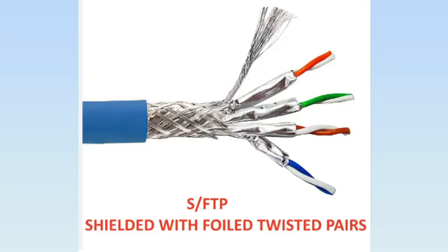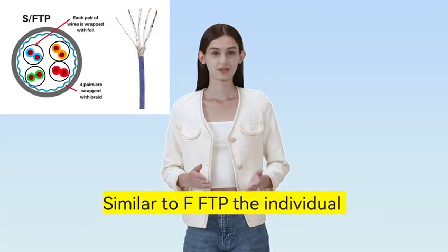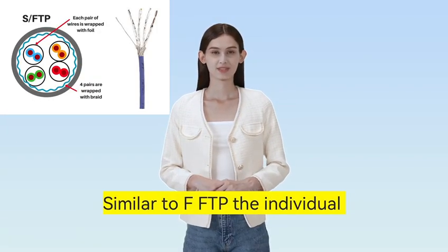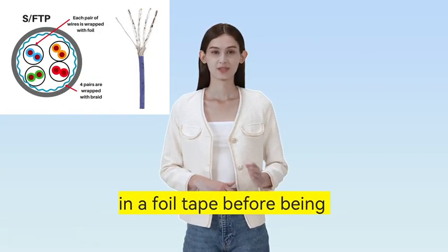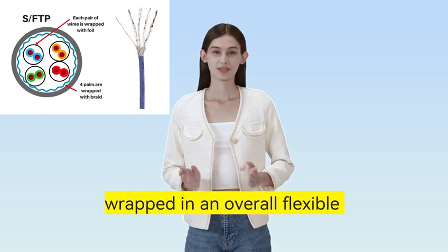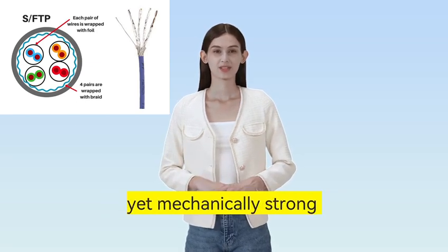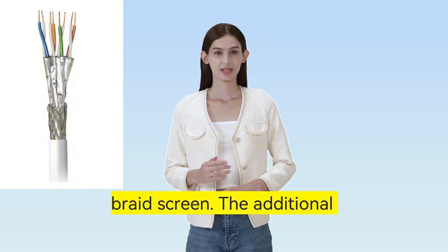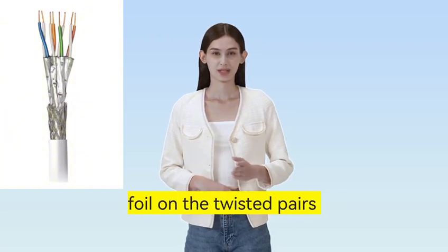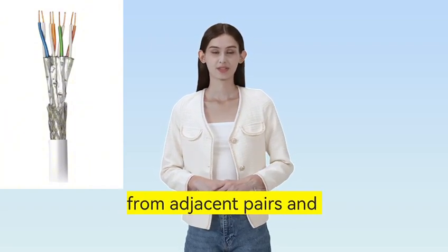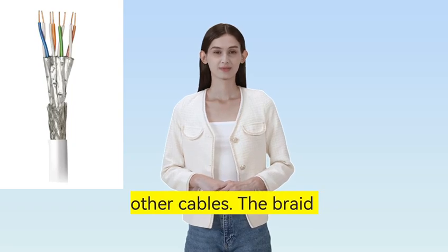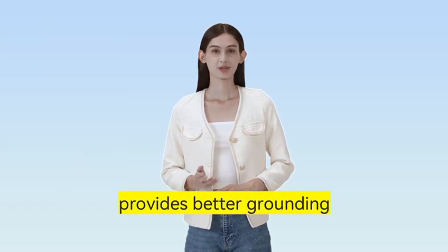S/FTP, shielded with foiled twisted pairs. Similar to F/FTP, the individual twisted pairs are wrapped in a foil tape before being wrapped in an overall flexible yet mechanically strong braid screen. The additional foil on the twisted pairs helps to reduce crosstalk from adjacent pairs and other cables. The braid provides better grounding.